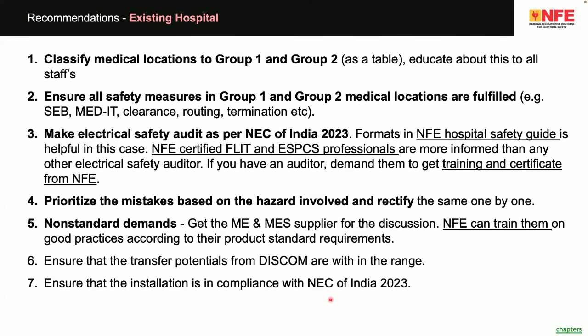Now, what kind of recommendations? In an existing hospital, the situation can be improved. First, the management should discuss with all the stakeholders, and they have to classify the medical locations, the electrical classification of medical locations, into group 1 and group 2 locations. You make it as a table and inform everybody, saying that, look, this is electrically a group 1 or group 2 location, and group 1 locations require X additional measures, group 2 locations require Y additional measures. In case of an accident in a group 1 location, what kind of measures can you handle? In case of a group 2 location, what kind of measures should you take? This can be educated. This is the first step.